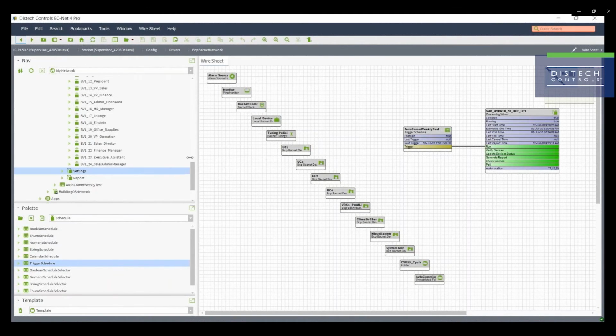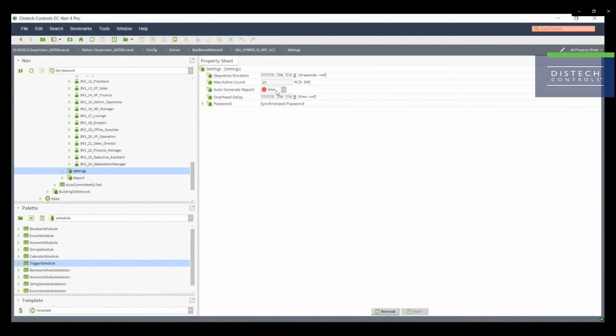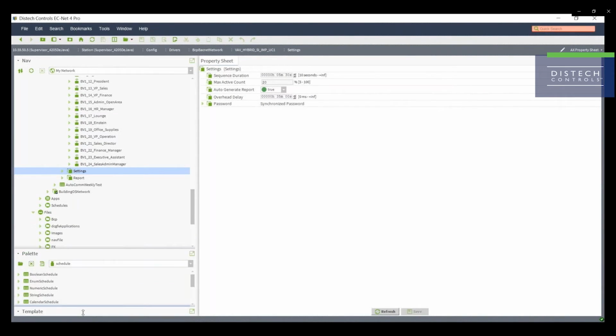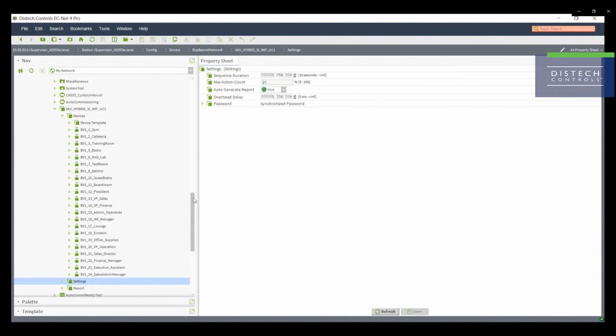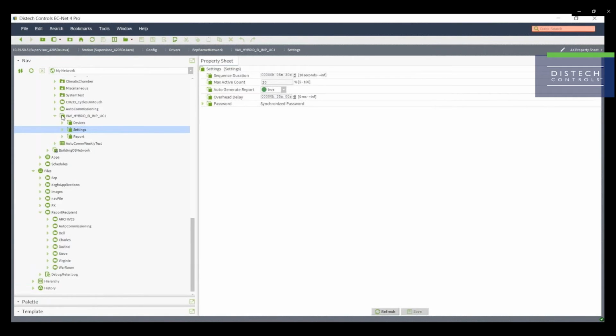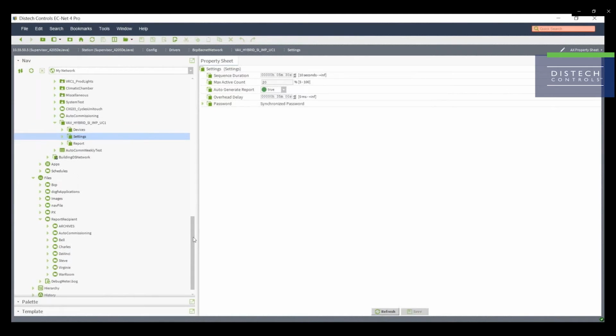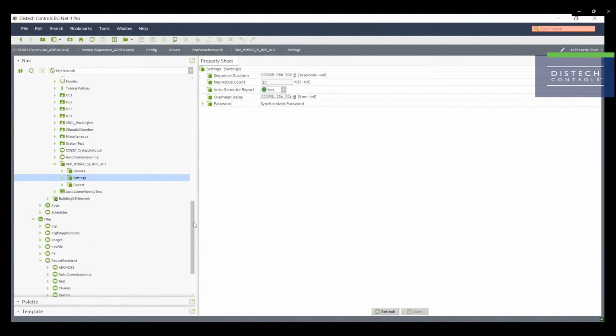Let's take a look at the settings property sheet one more time to set the auto-generate report to true. With this setup, our wizard will run every Thursday evening at 7 p.m. and it will automatically save a report to the files in this station. By default, the provided wizard templates are set up to save the reports automatically in the files folder in the station.